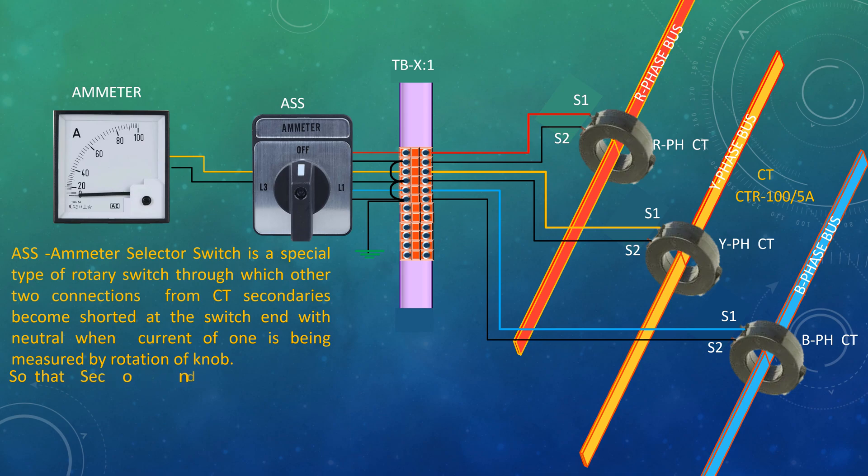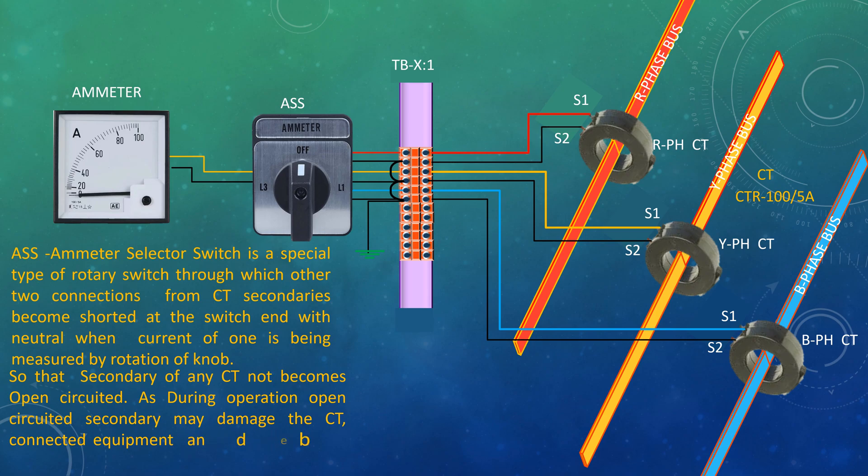During operation, an open circuited secondary may damage the CT, connected equipment, and may be dangerous to the operator.